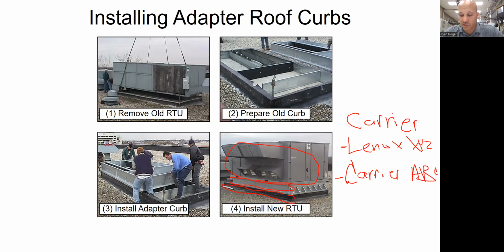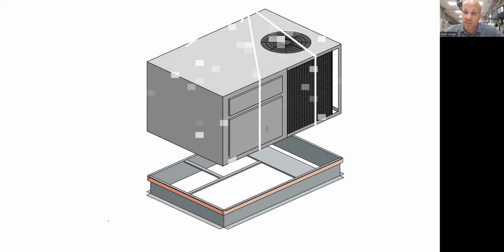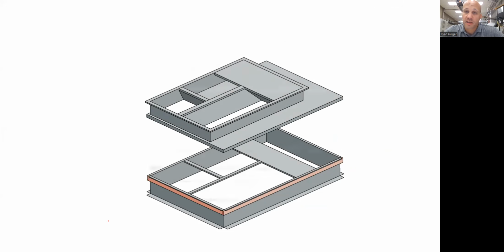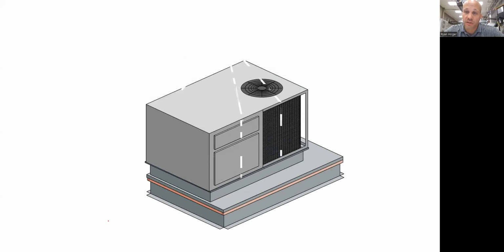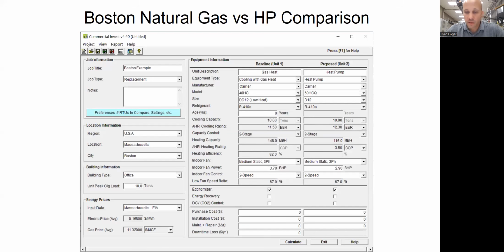If that scenario happened, like I just described, hey, I got this Carrier unit, 20 years later I replaced it with this Lennox and an adapter. Now it's 20 years later again. What I want to do is figure out what unit was underneath that Lennox originally, and get an adapter to that unit and skip this thing in the middle that I'm going to throw in the trash anyway. Right. So that becomes a little more challenging. Sometimes you can get that off the old blueprints, but usually in those cases, you need to field measure the curb and give the dimensions of what's underneath the adapter to the supplier so they can figure out what to put in there now. All right, let's see if there's any questions while we're here at the natural breaking point.